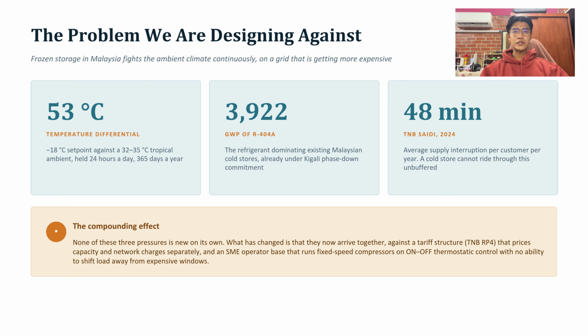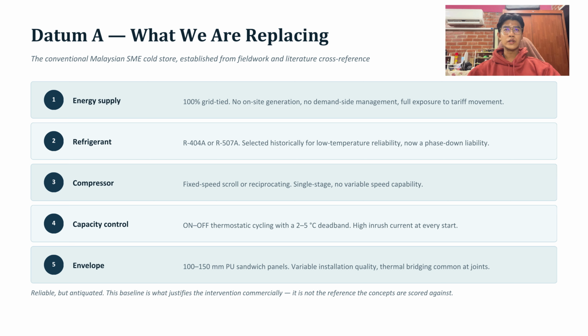The third one is the power grid is not perfectly reliable. According to TNB, there was an average 48-minute outage per customer last year. For a cold storage, even a short blackout without any backup power is a real risk to the stock. And here is the problem. None of these things are new. What is new is they are all happening at the same time, while the electricity tariff structure is also getting more complex, and most SME cold storage rooms are still using a very basic on-off control that cannot respond to any of this.